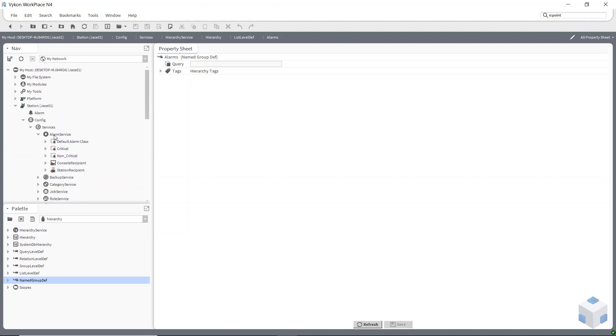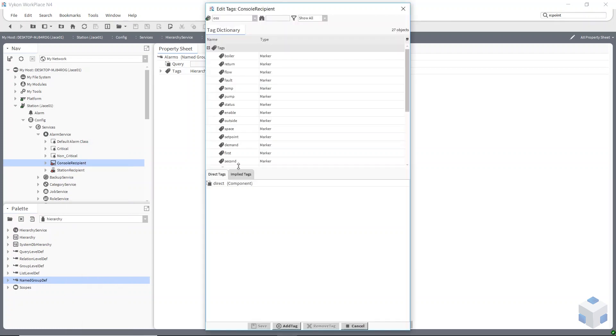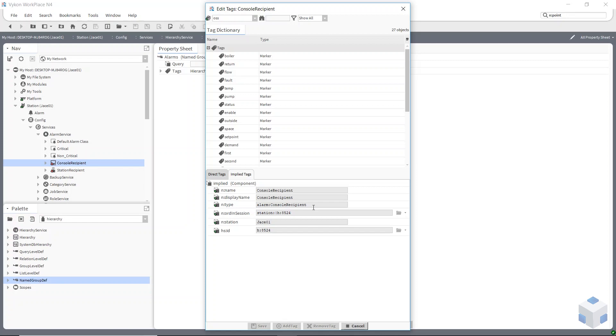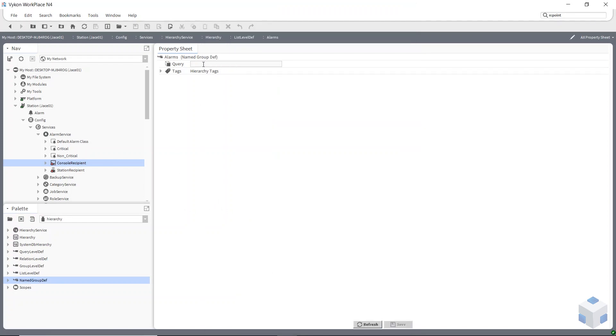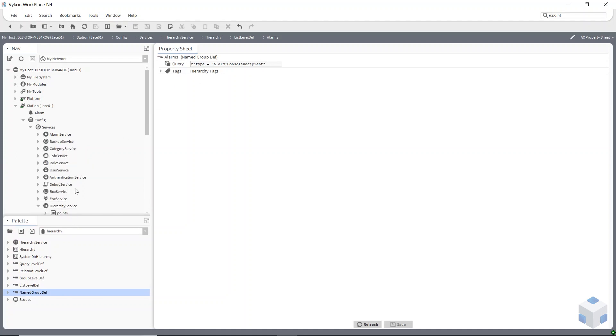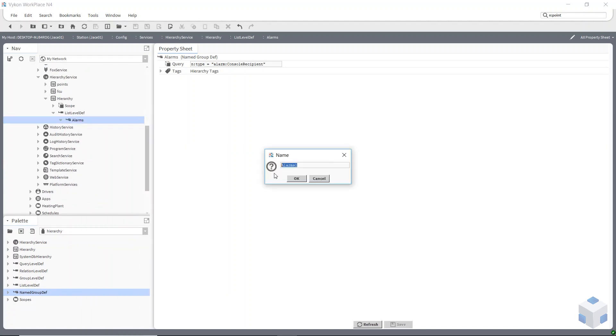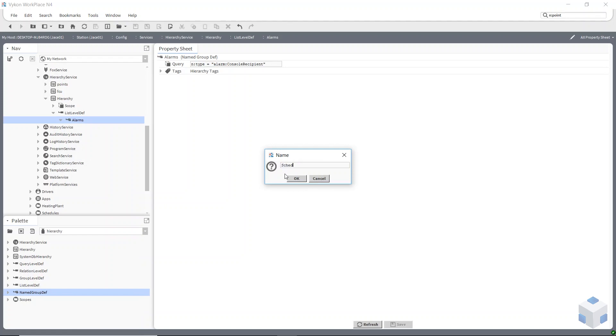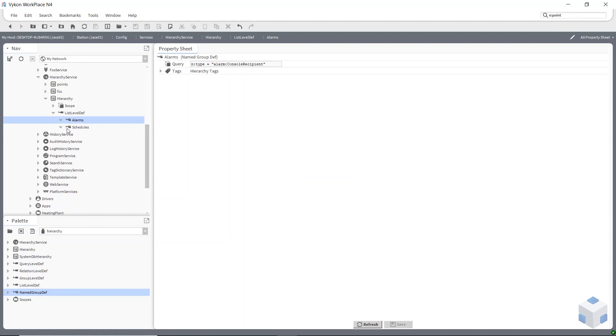Inside this named group level definition it's looking for a query. Go to your alarm console, right-click on it, look at the tags, and under implied tags you've got n colon type alarm console. Copy that text and put it in there as a query — it's an implied tag. You put equals, open speech mark, paste that in. This should bring back my alarm consoles. I can then duplicate that and do schedules — on my schedules I've added OnSite tags so I can change this query to schedule.